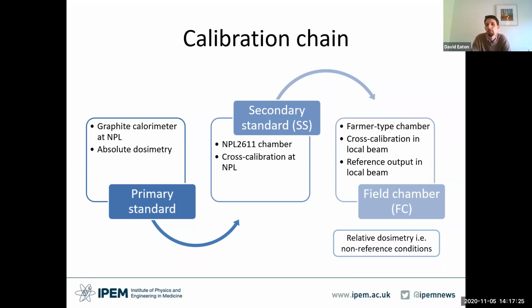When we receive that chamber back, we then spend a good amount of time on the Linac working through all our local chambers, which are typically a Farmer type chamber, but they could be another design as well. And we do cross-calibrations in our local beams. And once we have those calibration coefficients for our local field chambers, we can then use those chambers to measure and potentially to calibrate the reference output in our local beam. And we might also use those chambers for relative dosimetry as well in non-reference conditions.